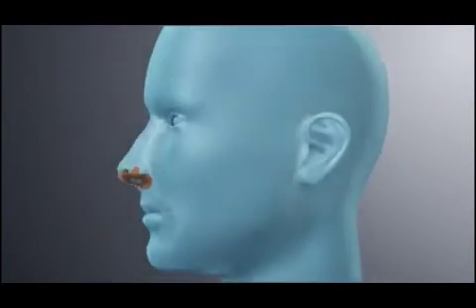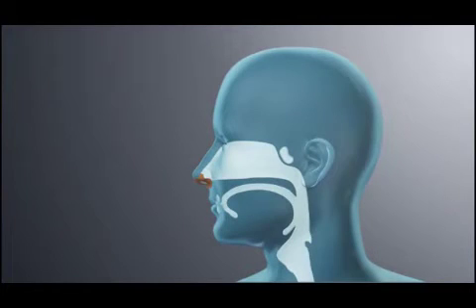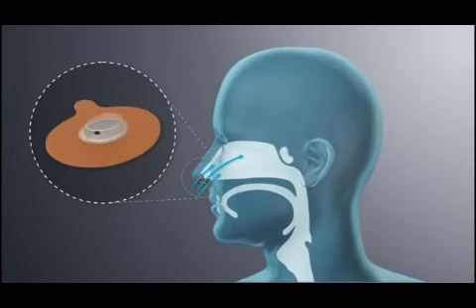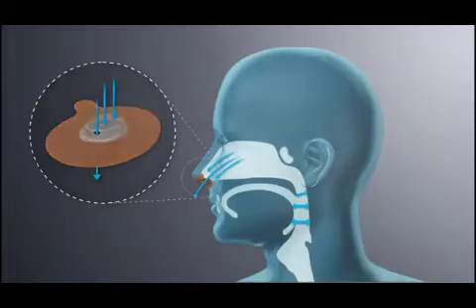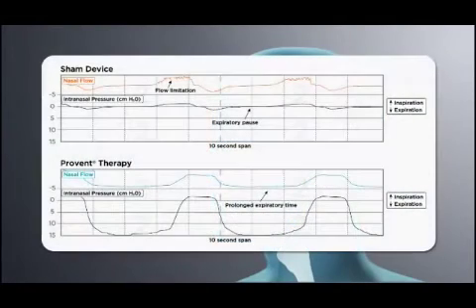The proprietary micro valve technology uses a person's own breathing to create EPAP. During inspiration, the micro valve opens, allowing for nearly unobstructed airflow. Then during expiration, the micro valve closes, partially restricting airflow to create EPAP and maintain pressure in the airway through the start of the next inspiration. This helps maintain airway patency during sleep.